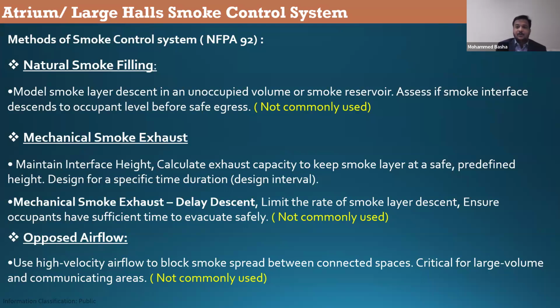We cannot allow the smoke to fill up to the bottom, which is not commonly used, but it can be used by accepting the proper fundamentals. And Qatar Civil Defense is not recognizing this method, but other jurisdictions are recognizing. For example, I'm in Riyadh here. Here, we do not have such stringent requirements. If you comply with International Building Code or International Code Council requirements, you can use this.